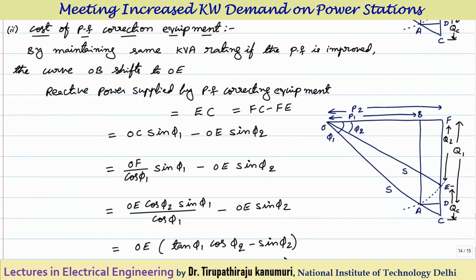Instead of expanding, if I improve the power factor using correction equipment — maintaining the same KVA rating — the curve OB will shift to OE. The reactive power that must be supplied by the power factor correcting equipment equals QC, which equals EC. This EC = FC − FE, because the reactive component that must be compensated is the difference between the reactive power at the old and new operating points.